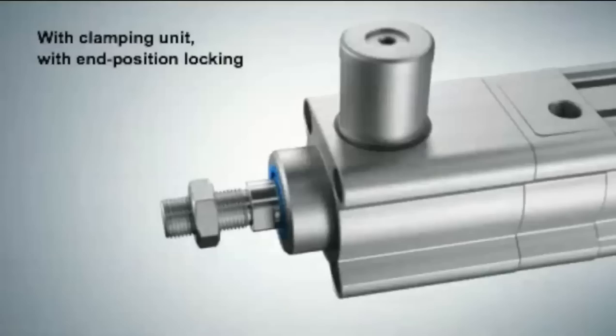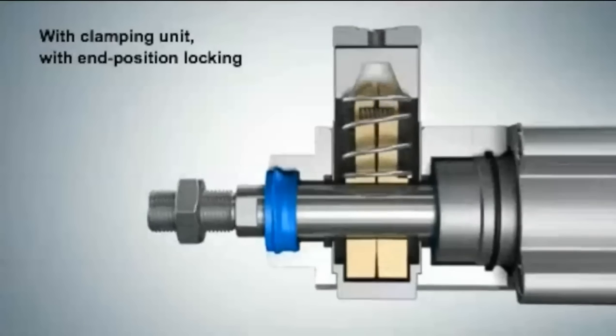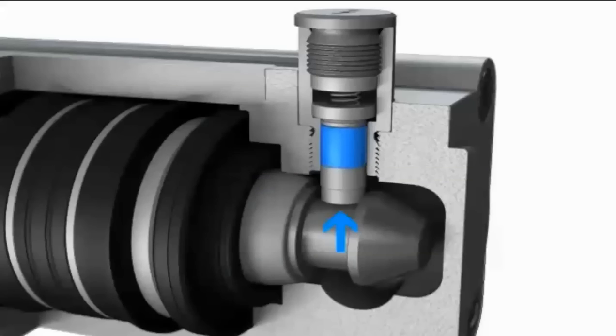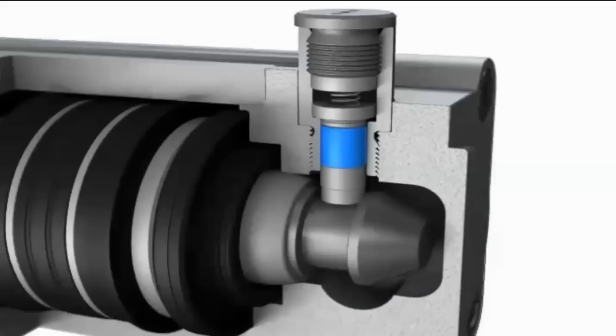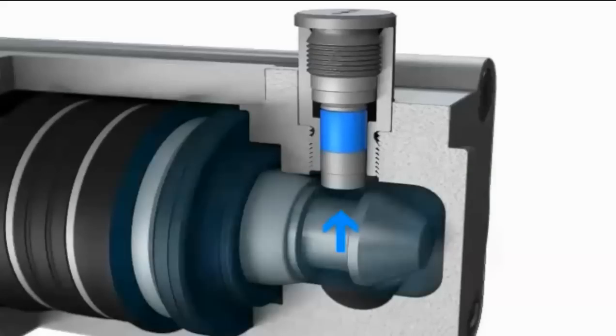A clamping unit is available which holds the rod in place if air pressure is lost, for example in vertical applications. A mechanical end-position lock is also available, which uses a pin to mechanically lock the piston rod each cycle.